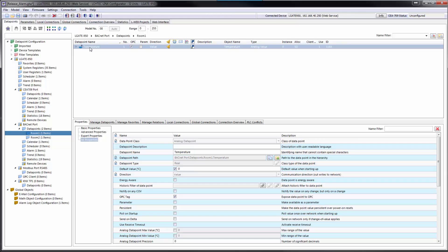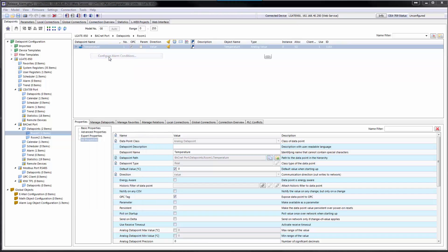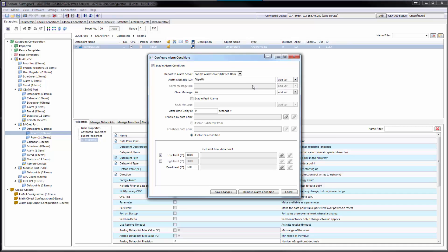The length of alarm messages has been extended to 250 characters. This comes in combination with a new path placeholder that can identify the data point path in alarm messages. This is beneficial for mass engineering alarm conditions on data points that have the same name but are located in different path locations.